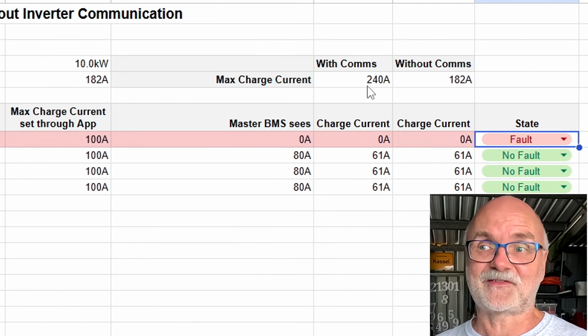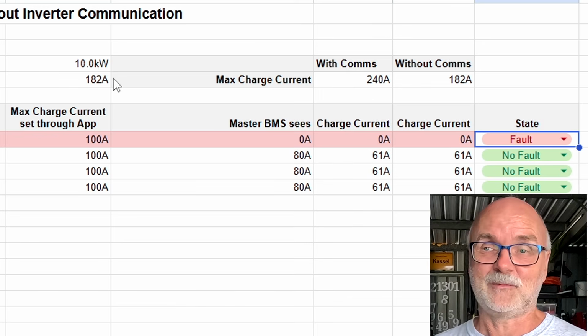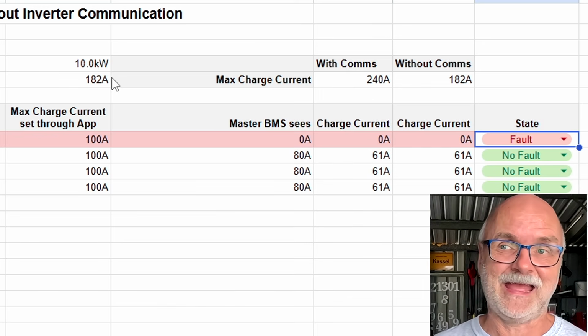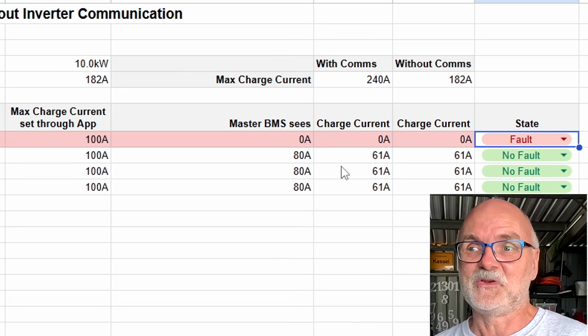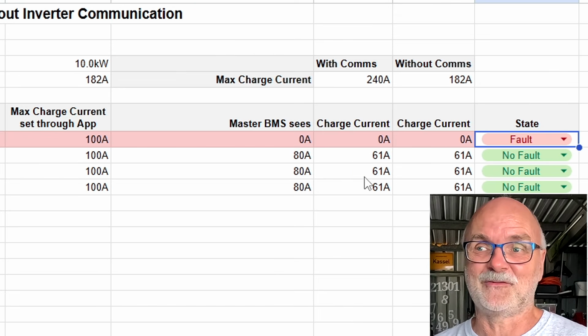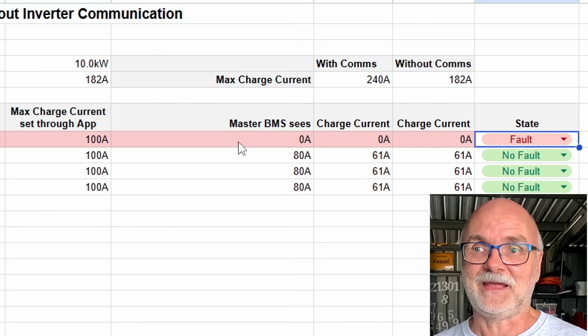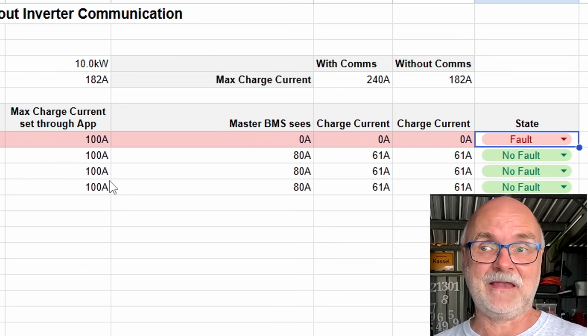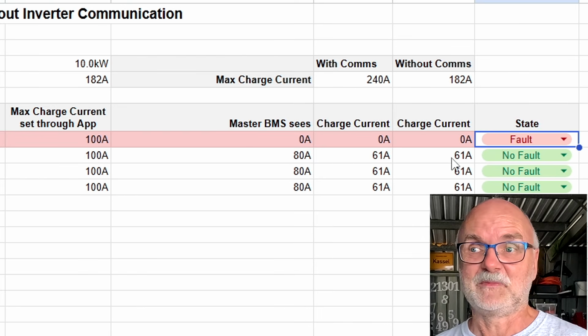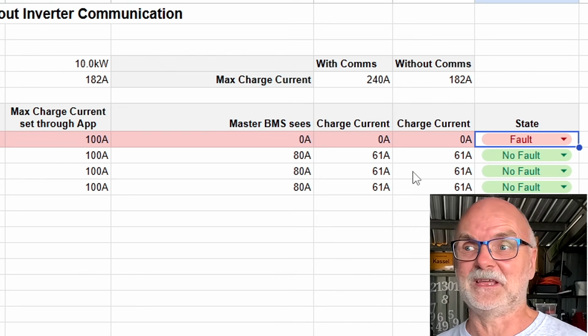Master BMS requests only 240 amps now, but we are still charging with only 180 amps from your solar system. No problems. 61 amps into the remaining batteries now. Yeah, that's 182 amps divided by 3 remaining batteries. 61 amps, still far under 100 amps. Same with communication, without communication.